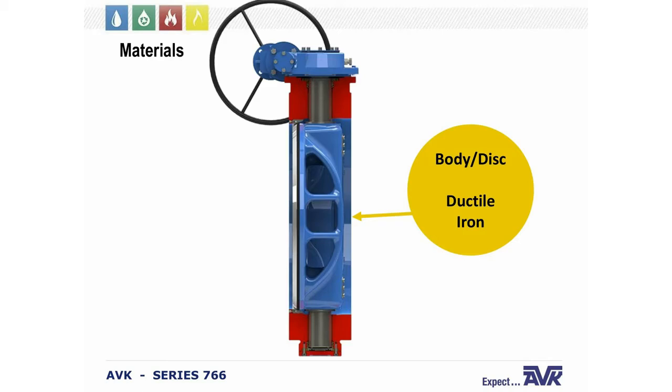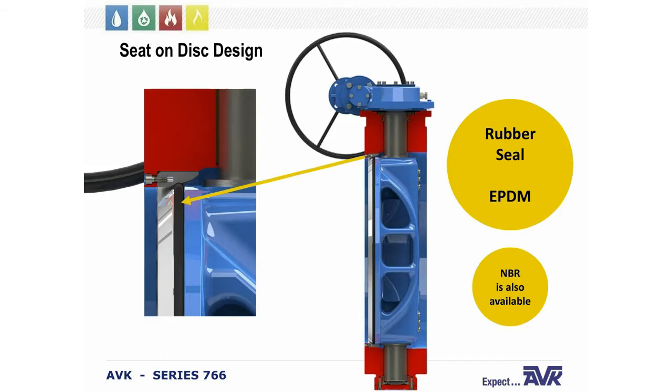The materials used for the valve: the valve body and disc are ductile iron. The AVK Series 766 is a seat-on-disc design. The seats are field repairable — either by injecting epoxy behind the seat or by replacing the seat completely. The rubber seals on the discs are EPDM rubber, but NBR is available.